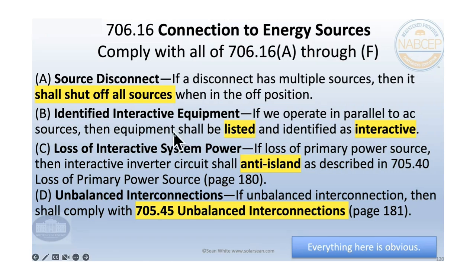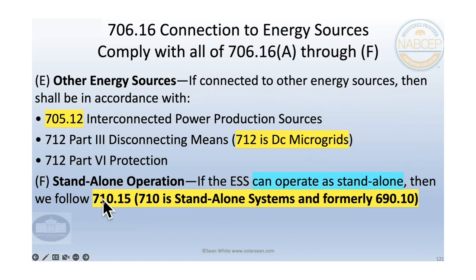Of course, things need to be listed as interactive if they're going to connect to the grid. Some of these things are just obvious. And unbalanced interconnections, I don't think there's much of a problem with that. Just like loads can be slightly unbalanced. You can have single phase loads on a 3-phase or split phase system. You can also have single phase interactive inverters on a 3-phase system. There's no rule against that.